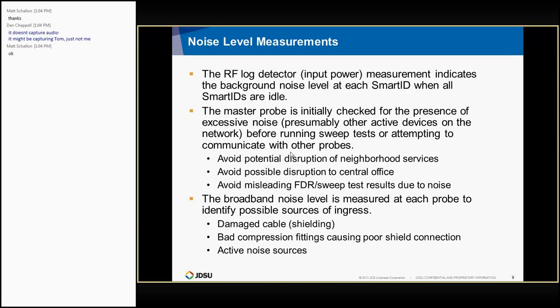So if there's excessive noise, then everything stops right then, and it just reports that there's too much noise on the network. That is different than the actual noise level measured at each probe during a test and subjected to a pass-fail condition. That's a much more refined measurement and will fail at a lower noise level. It will be marked as a failed test. So the broadband noise level measured at each probe is used to basically identify noise from damaged shielding, bad compression fittings, or active noise sources that are at a lower level.